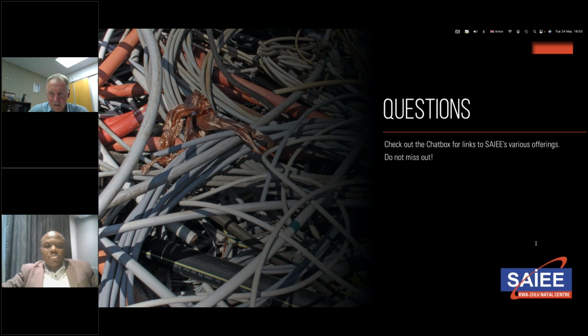Okay, then I think it is Mani that asked the question about the use of alternative metals and the possible reduction in new prices. So I think generally, if you move out of the mainstream and you're using alternative materials like Copper-Clad aluminium or Copper-Clad steel or aluminium alloys, or a mix of metal in the conductors, these tend to increase the price of the final product. Partly because the metals are more expensive. You're making something out of the ordinary, and it's mostly imported, these types of metals, or you have additional processes for tinning the conductor, and so on. So I would say, without a doubt, these things are more expensive generally than their copper counterparts, except for aluminium. If you make the change from copper to aluminium cables, there's a saving, definitely.